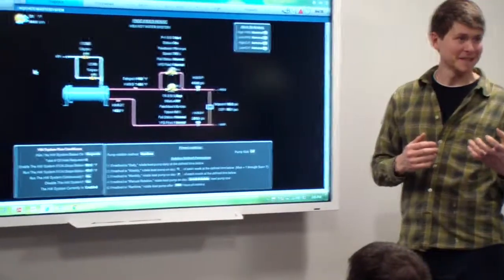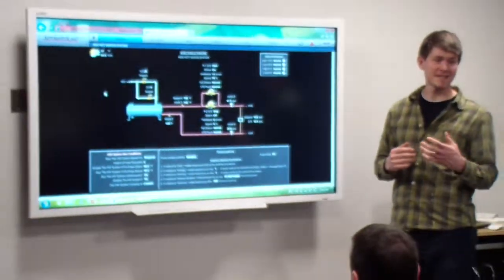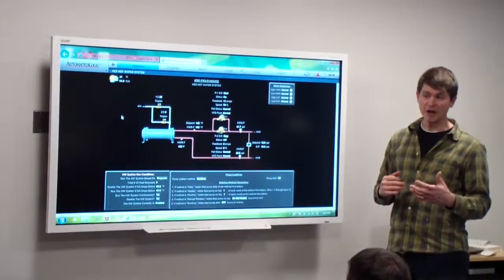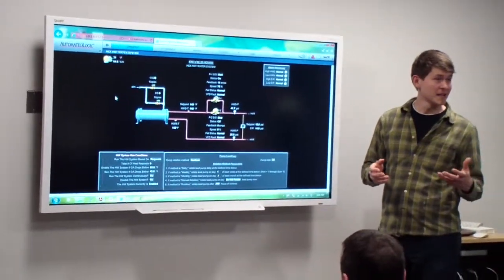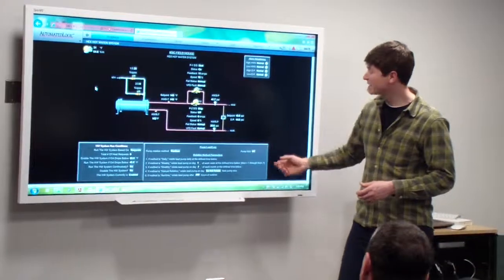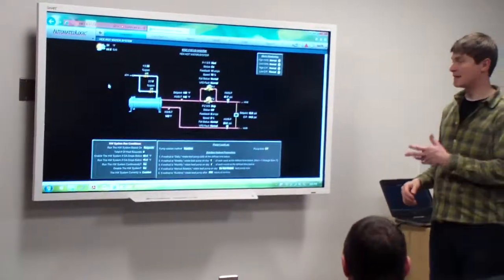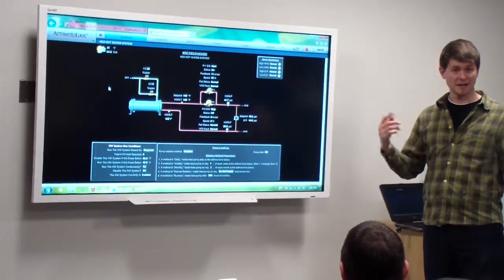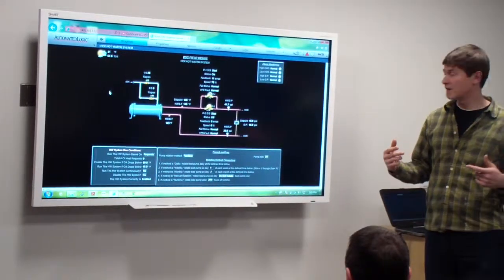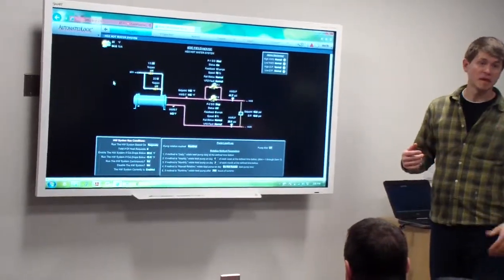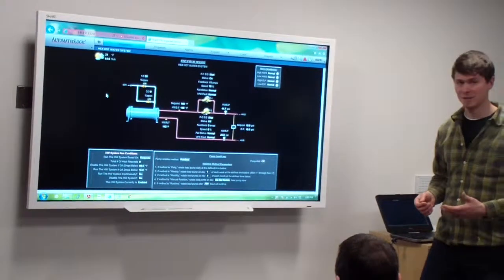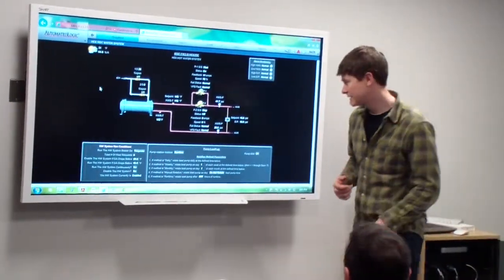So I was told that the water here has a lot of sediment in it, and it can get set up inside these pumps if they're not moved weekly or monthly. So what we've put in is a pump kick. Now throughout the summertime, as the heat exchanger is not running, you can click this and it'll actually circulate all of the hot water pumps that are in the building for, I believe, a 10-second period, just to make sure that they rotate.